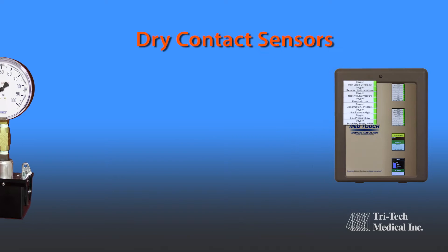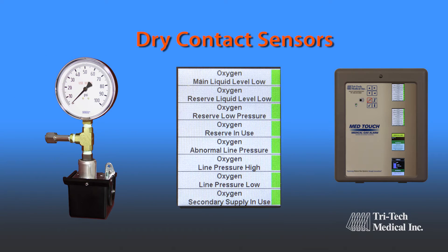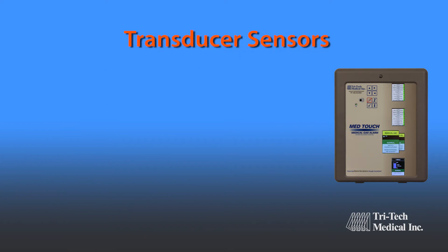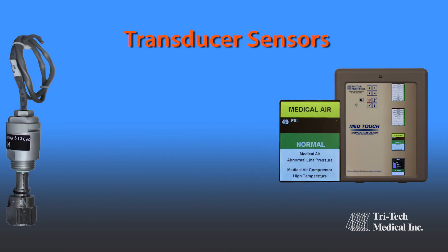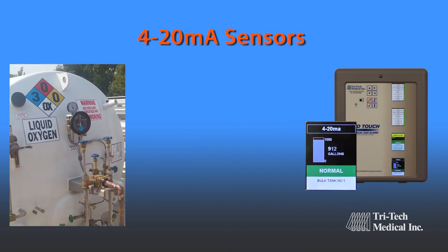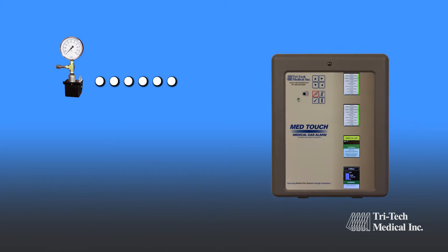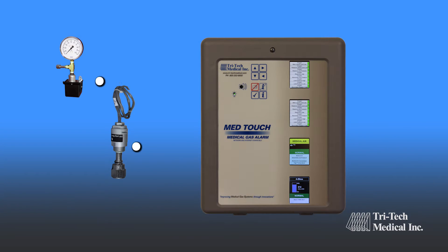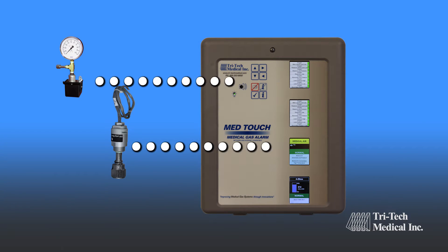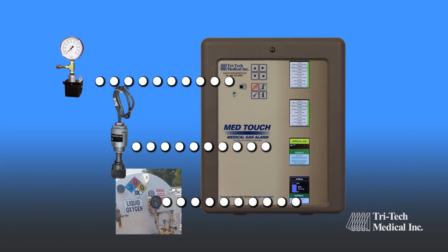Engineers and facilities have the choice of traditional dry contact sensors, transducer sensors, and 4 to 20 milliamp sensors, which can dynamically display liquid level, oxygen concentration, and numerous other applications. All three of these technologies may be incorporated into the same master alarm panel, providing additional vital information not previously available with dry contact only alarm systems.